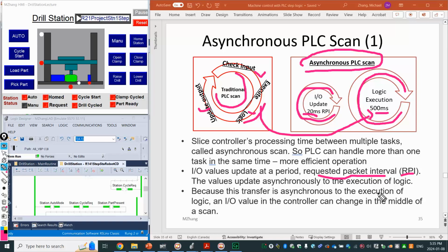Basically that means, as shown here, every 20 milliseconds the I/O will be scanned once, so this is faster than the logic - they run at different paces. That means your I/O may be updated during the execution of your logic.